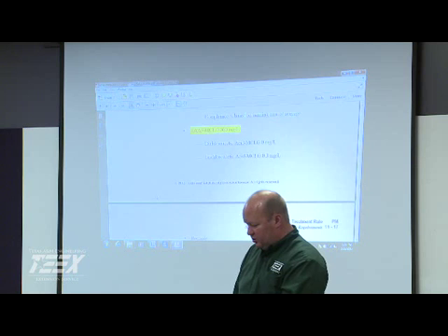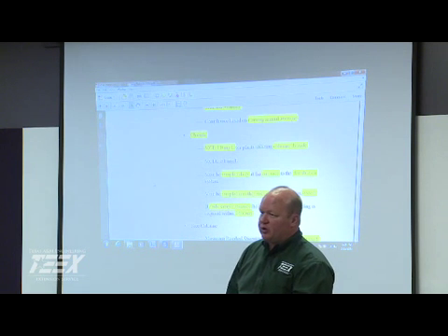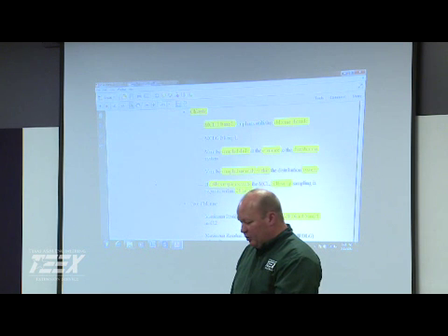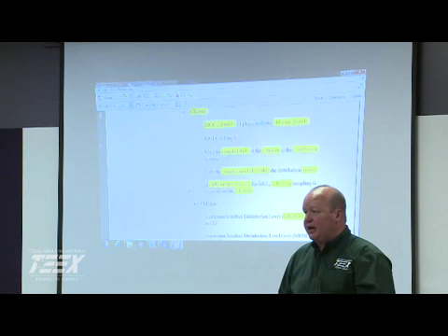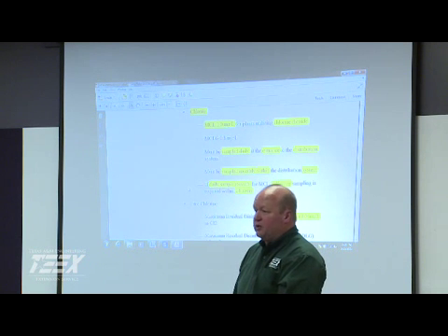Haloacetic acids is 0.06 for your MCL. Y'all aren't having any real issues with bromates and stuff, right? Nobody's using chlorine dioxide or very little, so you don't have any chlorite or chlorate issues. One of the big things with chlorine dioxide is if you're at 0.8, that's pushing it. Hit a 1, now you're going to be sampling every day and you have a lot of issues going on. So if you are using chlorine dioxide, you've got to keep a real close eye on your residuals.